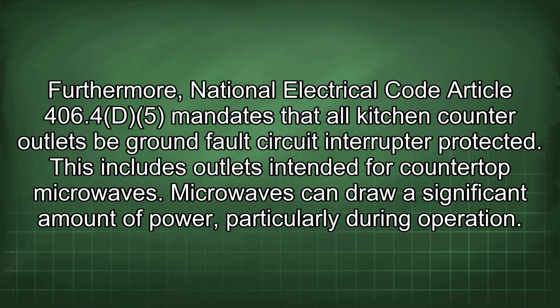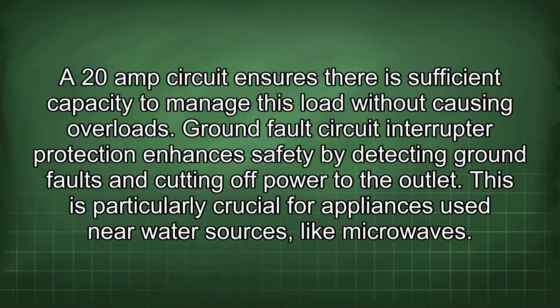Furthermore, National Electrical Code Article 406.4(D)(5) mandates that all kitchen counter outlets be ground fault circuit interrupter protected. This includes outlets intended for countertop microwaves. Microwaves can draw a significant amount of power, particularly during operation. A 20-amp circuit ensures there is sufficient capacity to manage this load without causing overloads.